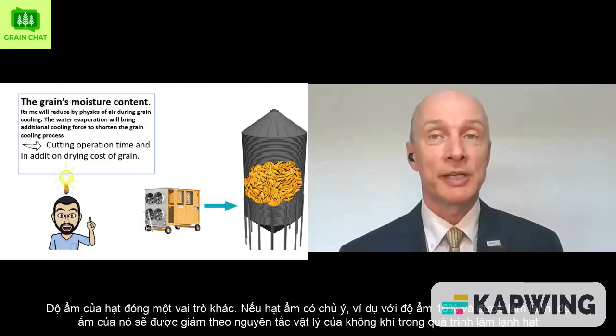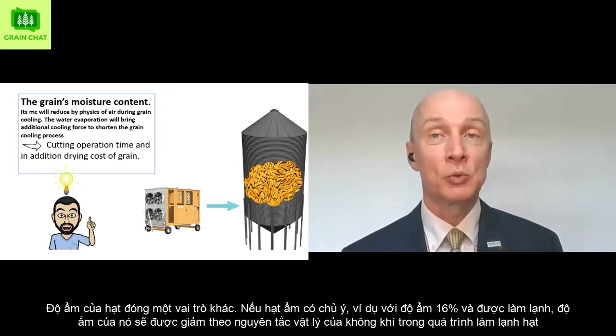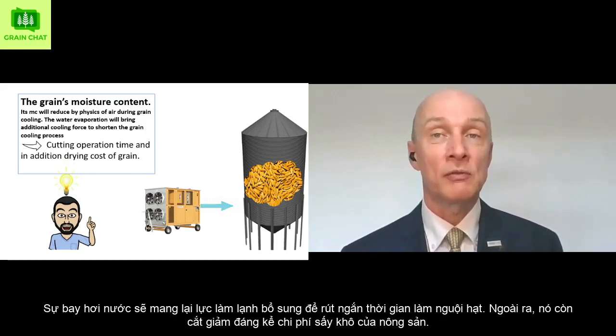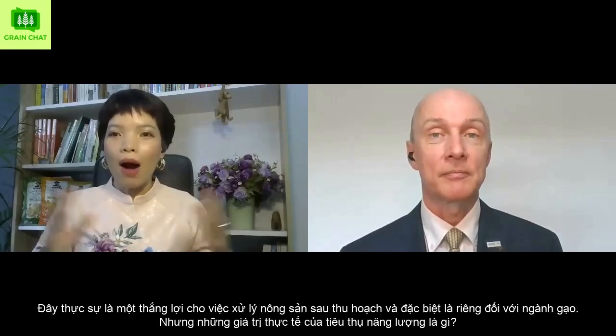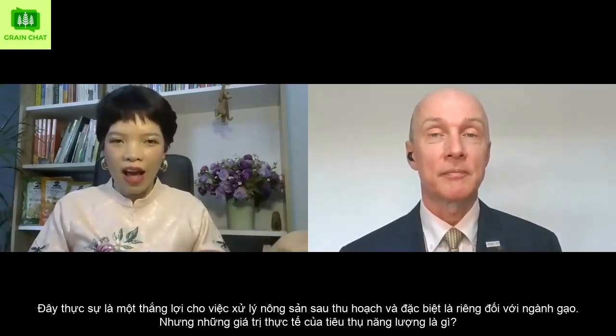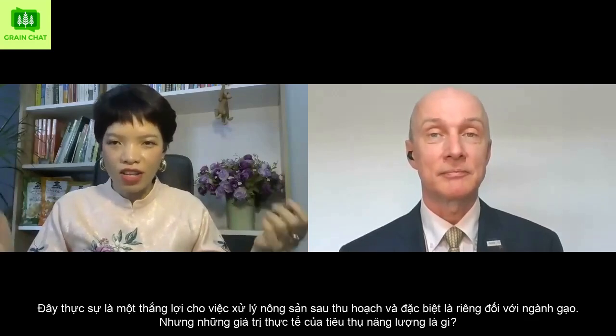The grain's moisture content plays another role. If moist grain, for example with 16% MC, is intentionally cooled, its MC will reduce by the physics of air during grain cooling. The water evaporation will bring additional cooling force to shorten the grain cooling process. In addition, it considerably cuts the drying cost of grain. Wow, that's really a win-win for the grain handling, in particular for the rice sector.